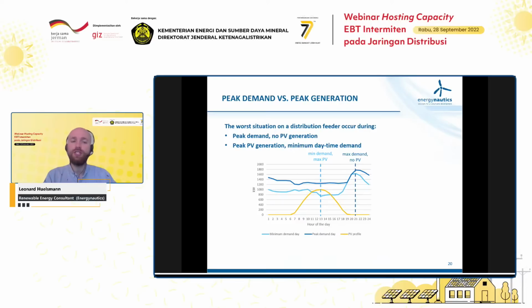And these worst situations would occur on the one hand during peak demand, when there's really maximum demand and there is no PV generation. And the opposite worst case situation would be maximum PV generation combined with a minimum daytime demand, because in this situation we may have the maximum amount of reverse power flows, and therefore the potentially worst situation.